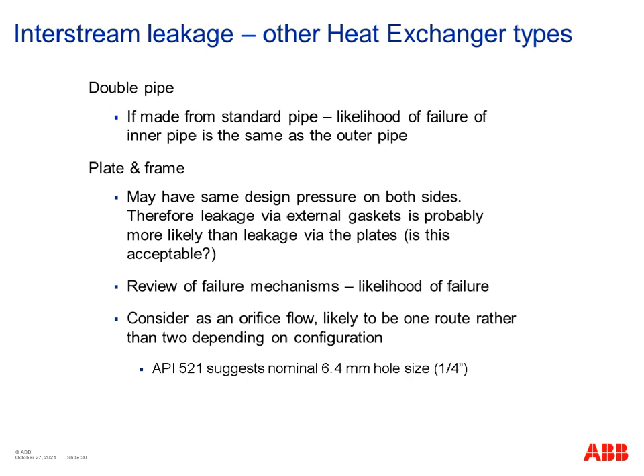For plate and frame exchangers and printed circuit exchangers, interstream leakage should though be considered. Holes between pressure systems can potentially form due to corrosion or fatigue or erosion. Unfortunately, the available guidance here is a little bit sketchy. So API 521 just recommends considering a hole of 6.4 millimeters to 25.4 millimeters. That's a quarter of an inch to an inch in diameter, and that's not particularly helpful.